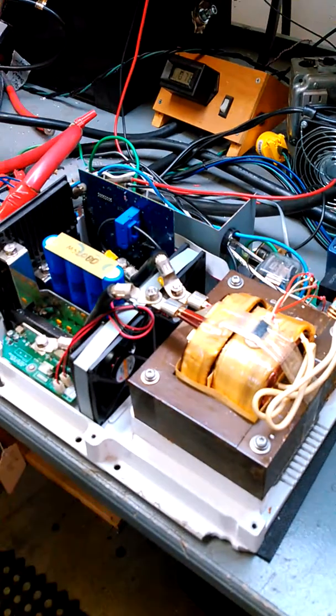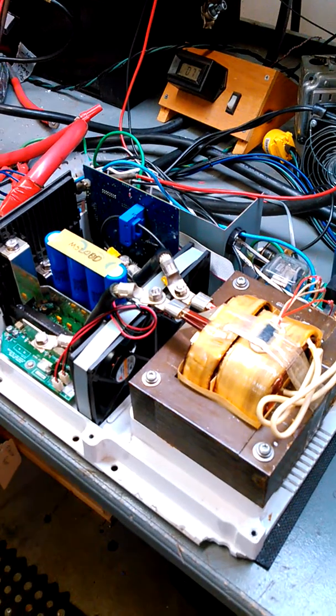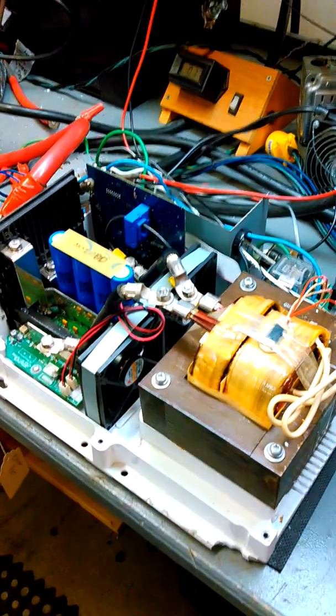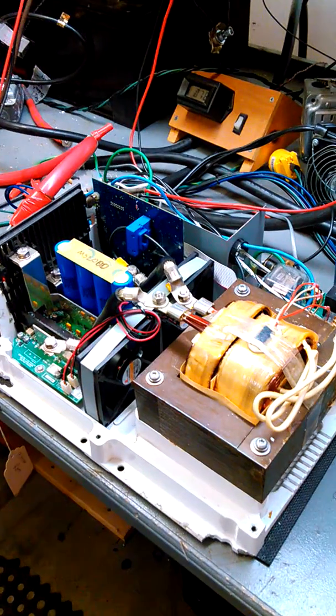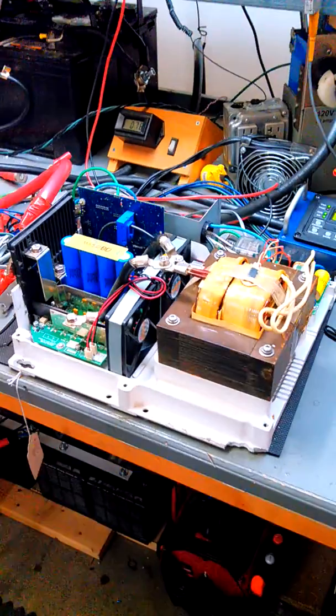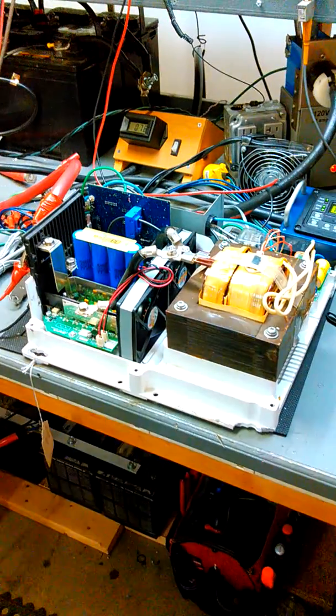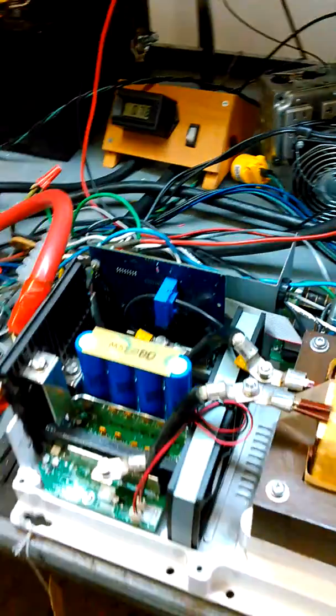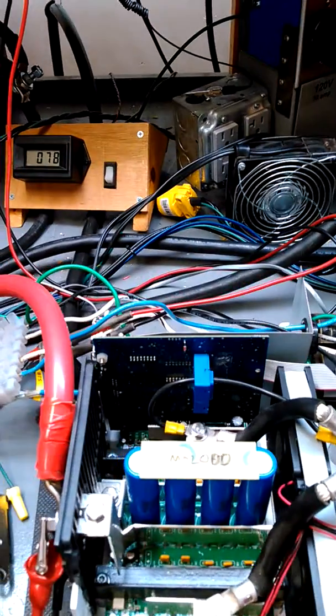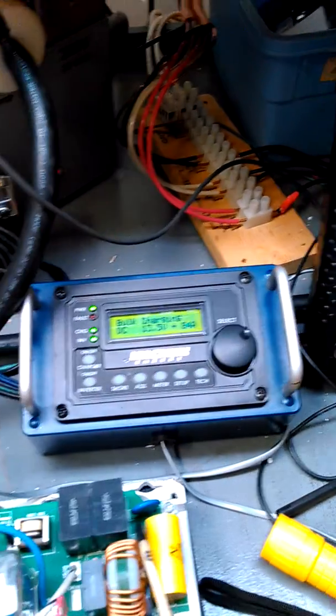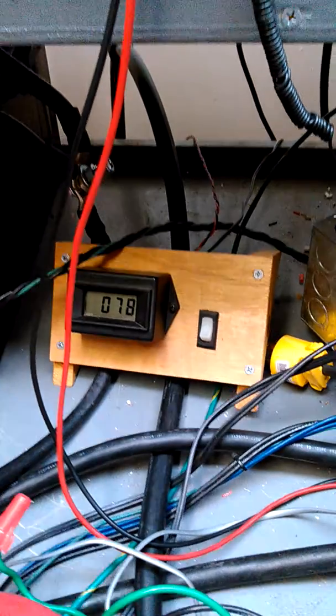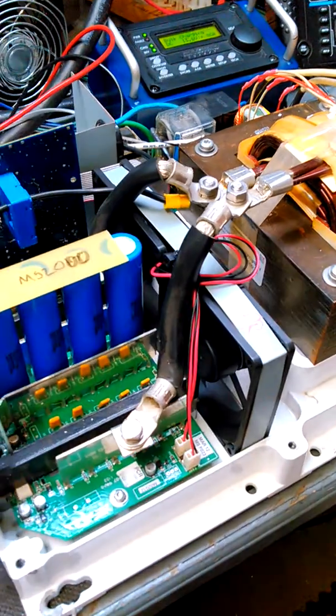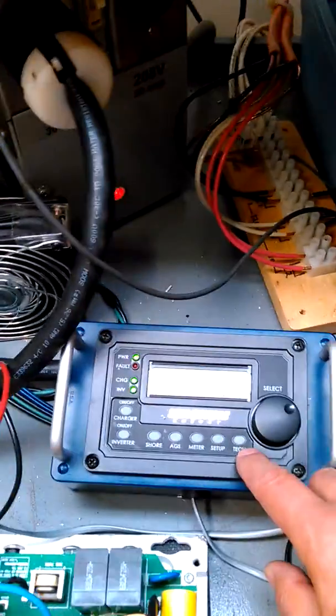So this one will go through a standard test of loading it up to 2,000 watts, which is what it's rated at, and running it through the charge cycle. Right now it's at bulk charging. We're at 78 amps going into the batteries. You can hear the fans are running pretty much full speed at this point on the Magnum unit.